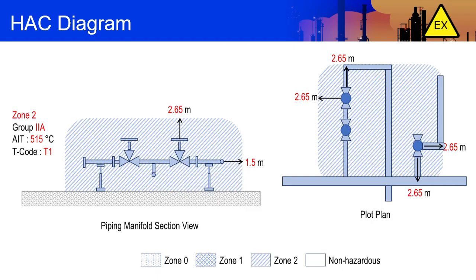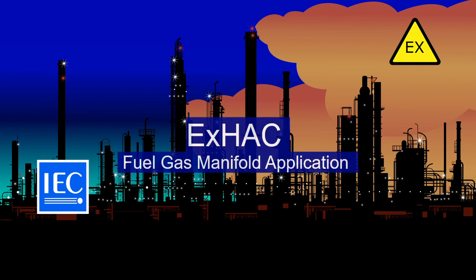If we apply shape A.2 to our manifold example, the classification degree and extent will look like this. A 2.65 meter Zone 2 classification extent surrounds all release sources on the manifold. The group classification is defined as IIA, and the auto-ignition temperature for the application is 515 degrees Celsius, corresponding to the T1 temperature code. Our hazardous area classification design for this natural gas manifold is now complete.